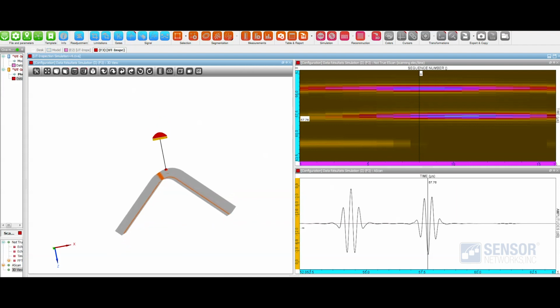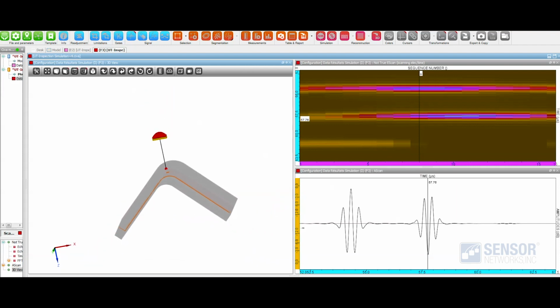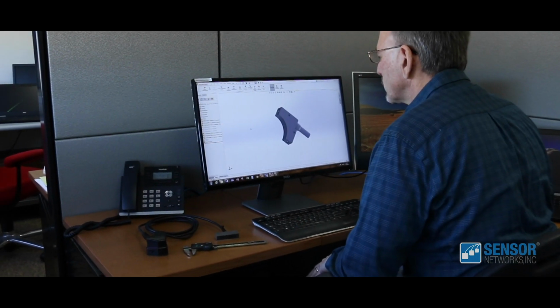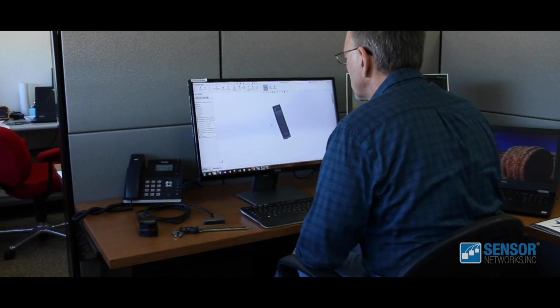Once the customer requirements are established, we input the proposed phased array acoustic design and virtual test piece into CIVA 2D and 3D simulation software to verify that the design is appropriate to satisfy the required performance. As needed, iterations are made to optimize before mechanical designs are created. Mechanical component designs are then created in SOLIDWORKS.